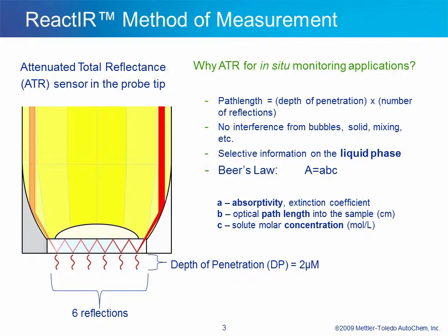I will cover the method of measurement briefly. For those that want more detail, please visit the reaction analysis page on mt.com. The technique used in our sampling technology is attenuated total reflectance, commonly referred to as ATR. ATR works on the principle of Snell's Law, where each reflection is actually an interrogation point of the sample matrix. At each interrogation point, the infrared radiation penetrates into the reaction matrix only about 2 micrometers. Therefore, the path length is equal to the depth of penetration times the number of reflections. Since the infrared radiation only penetrates such a short distance, bubbles and solids do not affect the measurement.